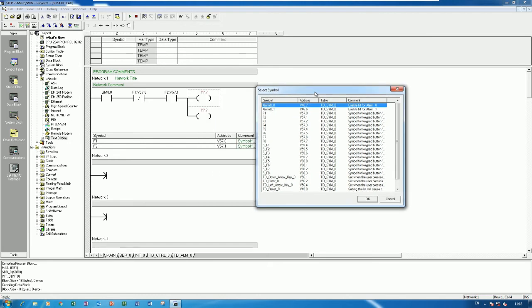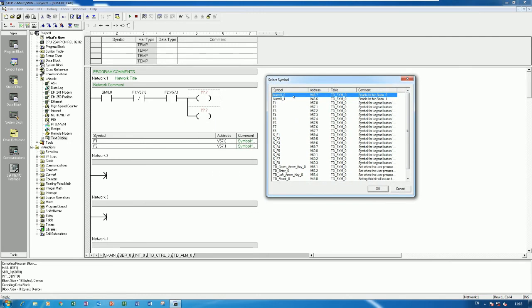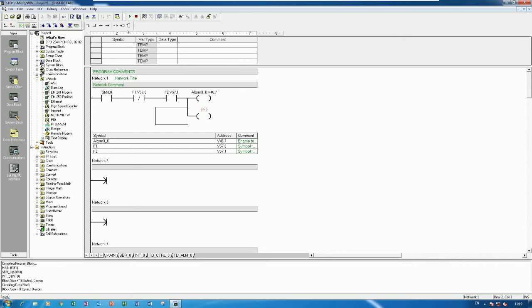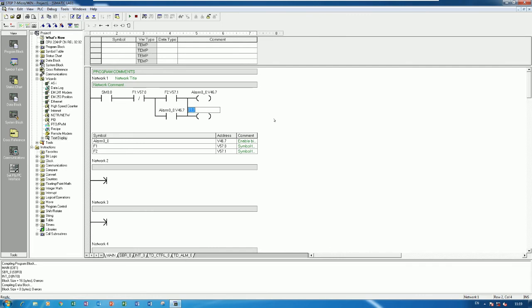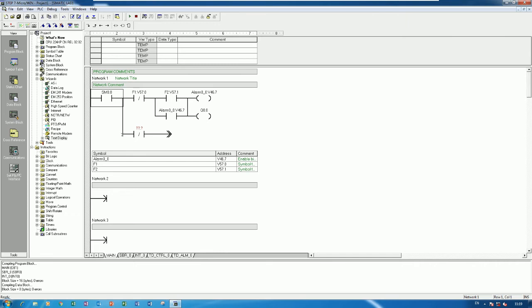Then I will hold the signal using the alarm. I will choose Alarm 0 for motor status start, which we already set up, and then hold the signal using Alarm 0. Here is the output we want to start the contactor or relay to control the motor - in this case I will use Q0.0 for starting the motor.